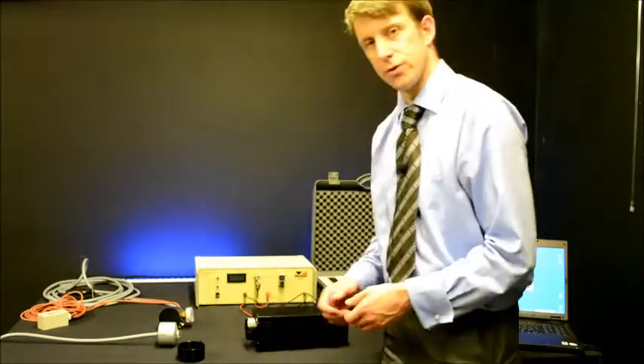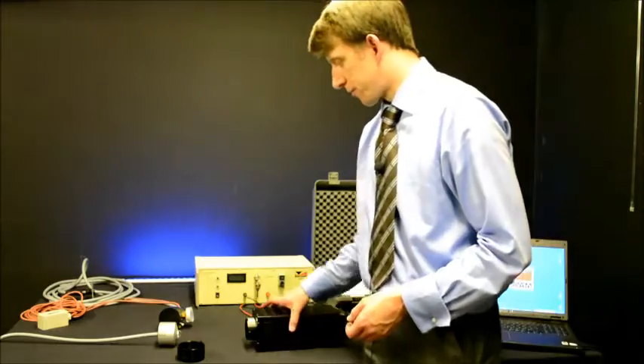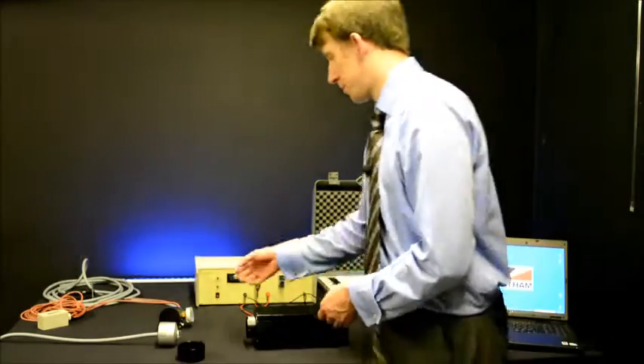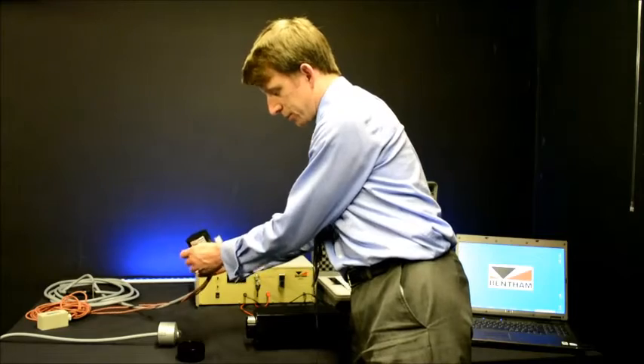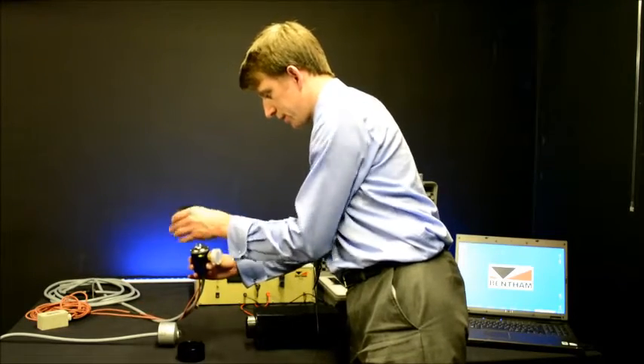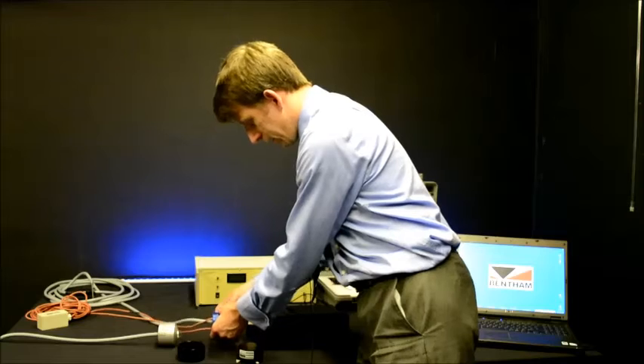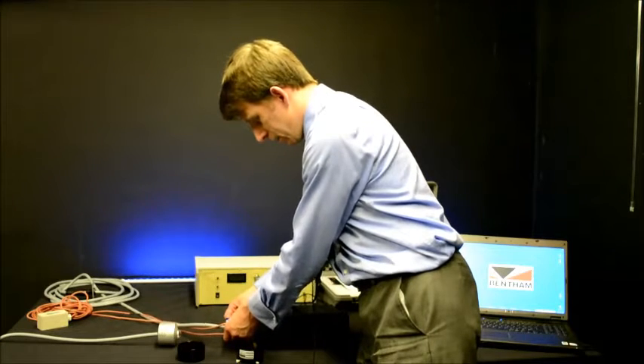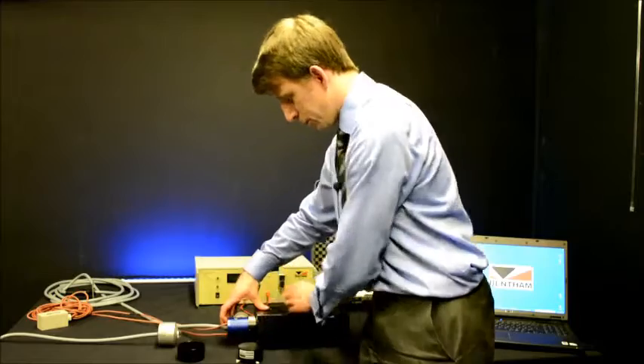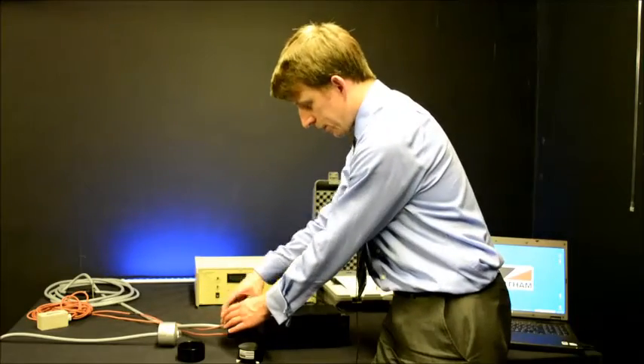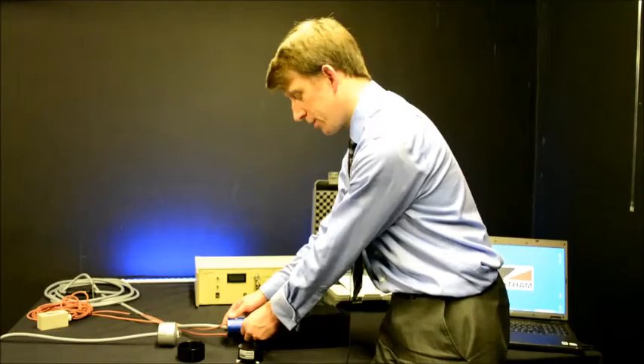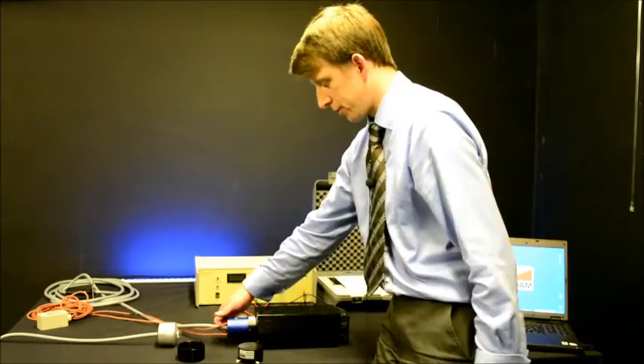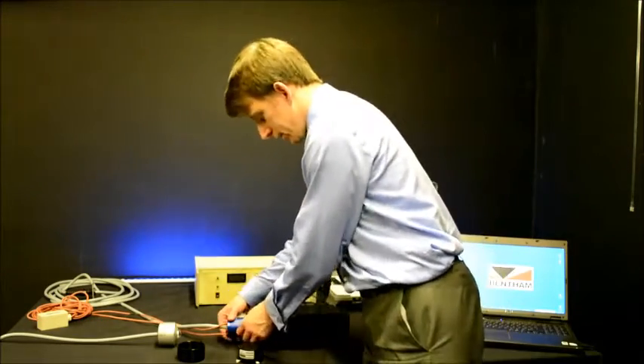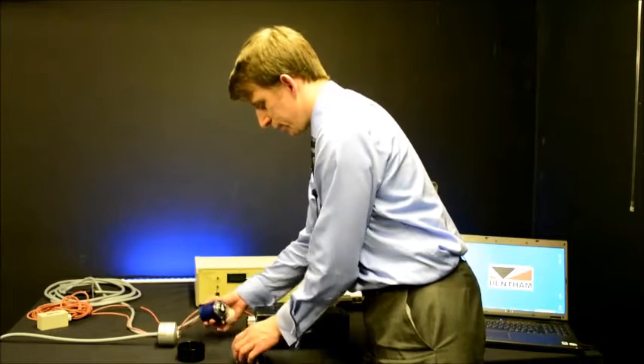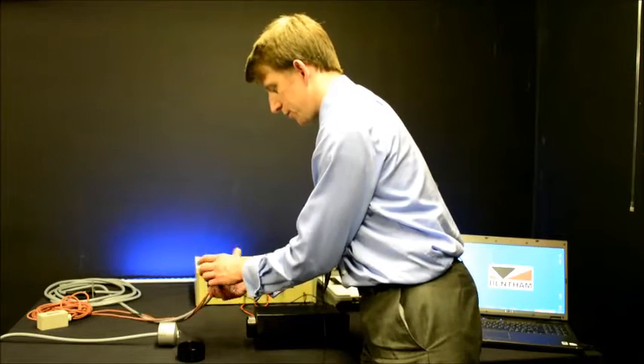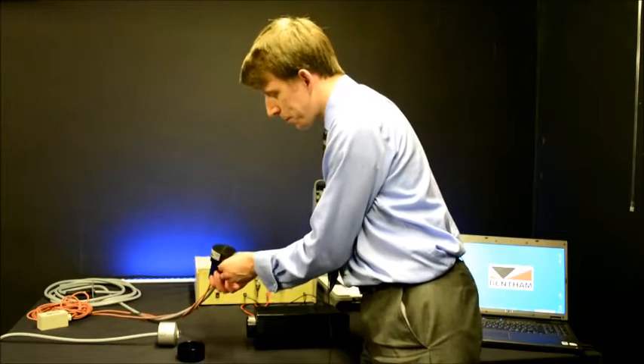So, for example, now we've installed the diffuser for use with the Schrader input optic. One can simply remove the protective cover from the Schrader input optic and very, very carefully install the diffuser, pushing as far as one can go, keeping the desiccant away from the thumb screw so one can attach the diffuser well. And likewise, removing very gently to ensure the quartz dome is not damaged.